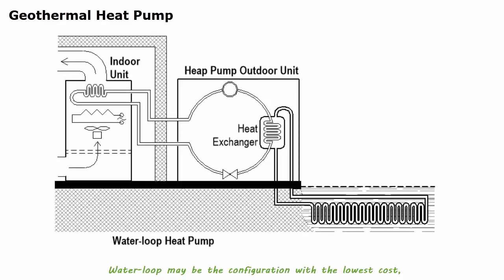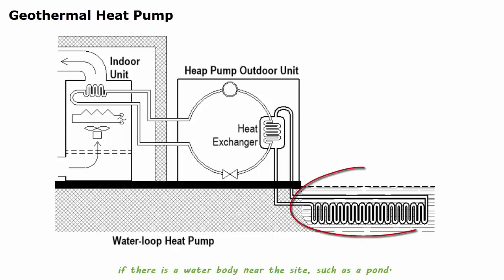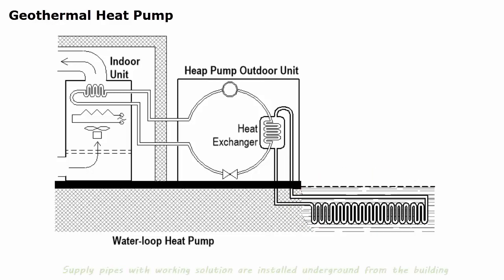Water loop may be the configuration with the lowest cost if there is a water body near the site, such as a pond. Supply pipes with working solution are installed underground from the building to the water and shaped into coils. They are placed at least 8 feet under the surface to prevent freezing.